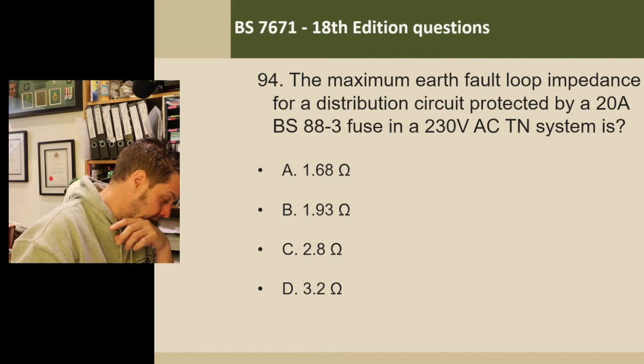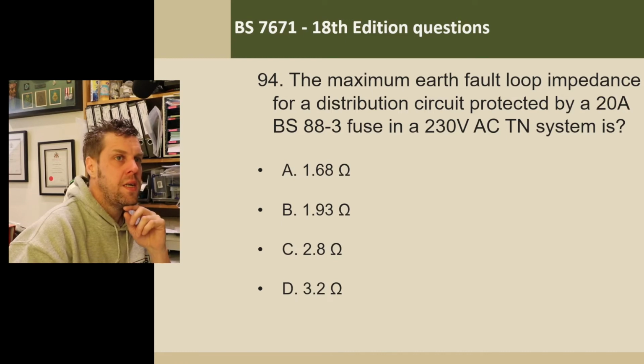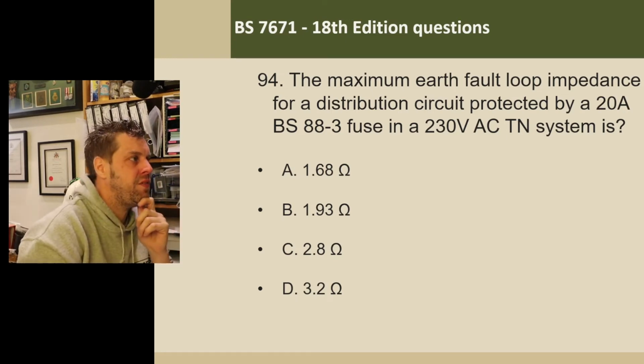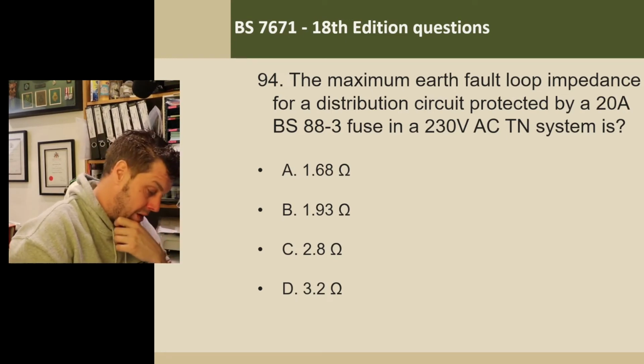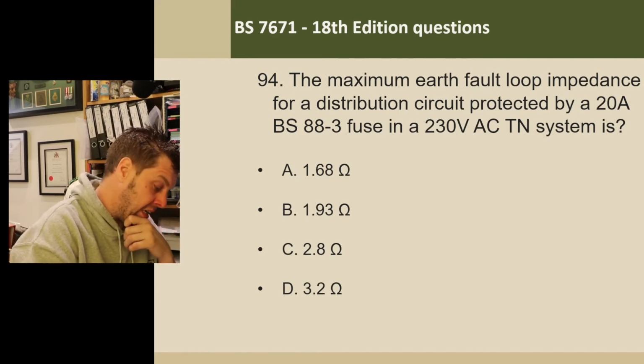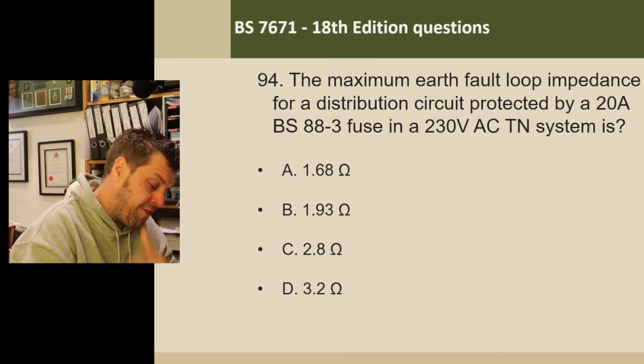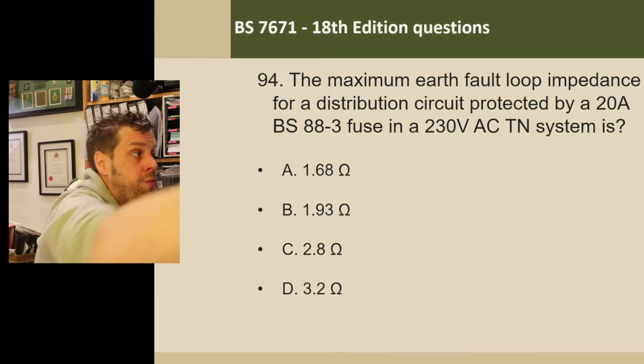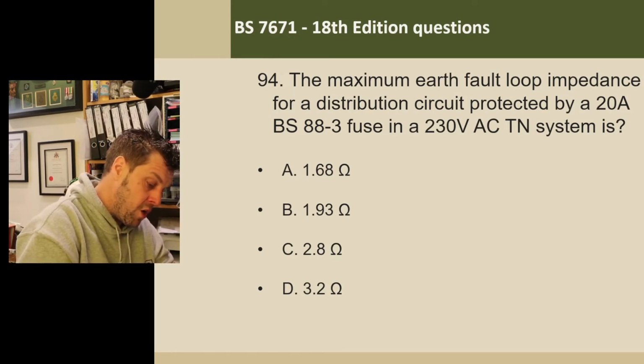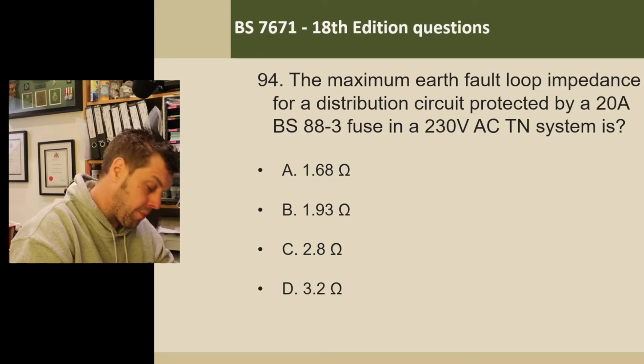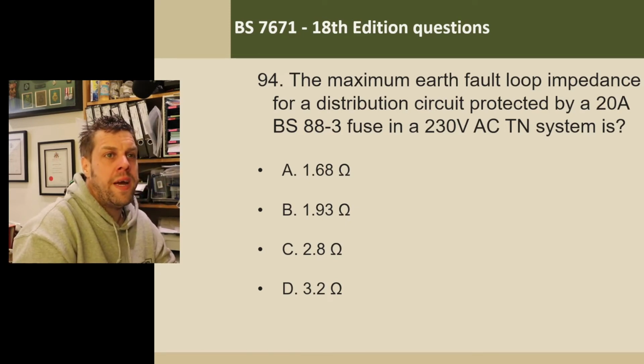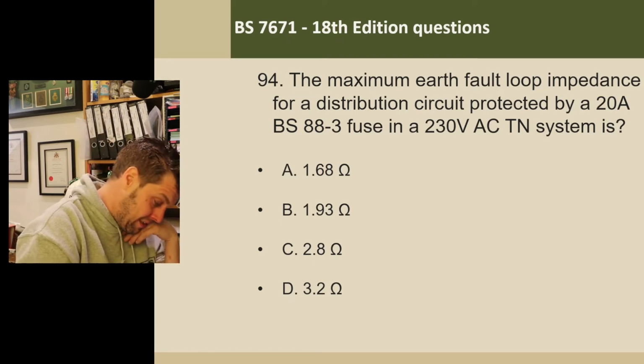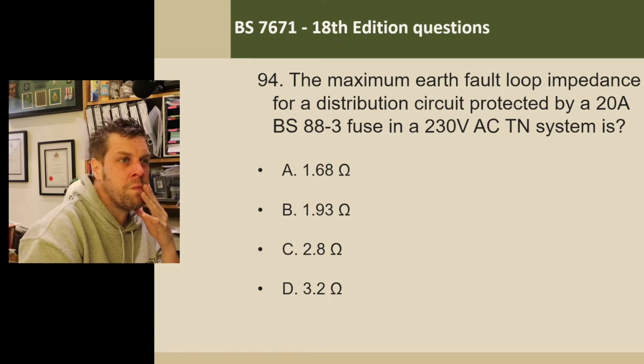Let's try 41.3. Maximum earth fault loop impedance for circuit breakers. Well, this says the 20 amp BS 88-3 fuses, so I don't think it's going to be off table 41.3. Table 41.4 says maximum earth fault loop impedance, which is what I'm after, for fuses, which is what I'm after, for a 5 second disconnection time, distribution circuit, that's what I'm after, with a UO of 230 volts, yep, in a TN system, which is not specified, so I'm assuming it's all.